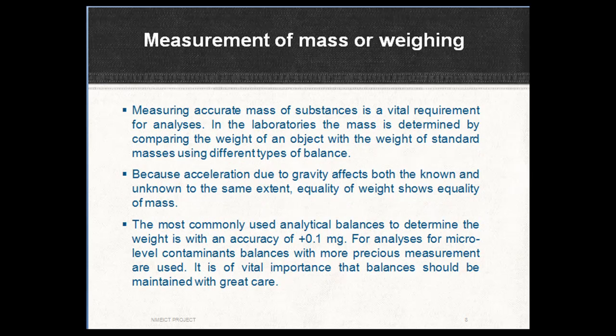Measuring accurate mass of a substance is a vital requirement for analysis. In the laboratory, the mass is determined by comparing the weight of an object with the weight of a standard mass using different types of balance. Because acceleration due to gravity affects both the known and unknown to the same extent, equality of weight shows equality of mass. The most commonly used analytical balance determines weight within an accuracy of 0.1 mg.